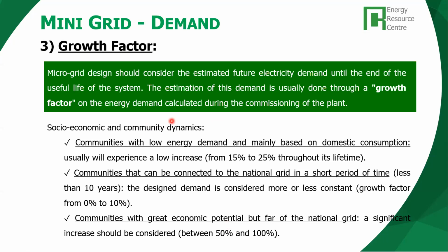What we can see are some references. If we have communities with low energy demand and their demand is basically residential, domestic, you can expect a low level of increase of the demand. Low level means from 15 to 25% of increase, especially in the first 5 years of operation of the mini grid. If you have, on the contrary, communities that can be connected to the national grid very soon, 2 years, 5 years, less than 10 years, the design demand will be more or less constant. Okay, the growth factor could be very little.